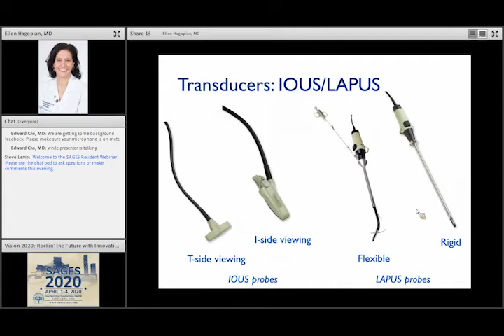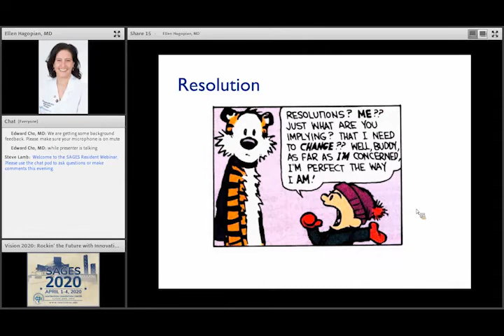So let's talk a little bit about resolution. Resolution of the image in ultrasound is obviously one of the most important things, is optimizing your image in addition to being able to interpret your image. So let's talk a moment about low frequency versus high frequency. High frequency probes have better image resolution, as opposed to low frequency probes have less image resolution. The reason for this is that low frequency probes, which are usually 3 to 5 megahertz or so, have a much longer wavelength. And because they have a longer wavelength, they have less image resolution. However, because the sound attenuates less, they have deeper penetration.